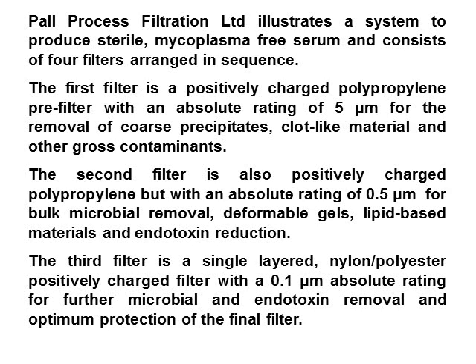A process filtration system illustrates a four-filter sequence to produce sterile, mycoplasma-free serum. The first filter is a positively charged polypropylene pre-filter with an absolute rating of 5 microns, for the removal of coarse precipitates, clot-like material, and other gross contaminants. The second filter is also positively charged polypropylene but with an absolute rating of 0.5 microns, for bulk microbial removal, deformable gels, lipid-based materials, and endotoxin reduction. The third filter is a single-layered, nylon/polyester positively charged filter with a 0.1 micron absolute rating for further microbial and endotoxin removal and optimal protection of the final filter.